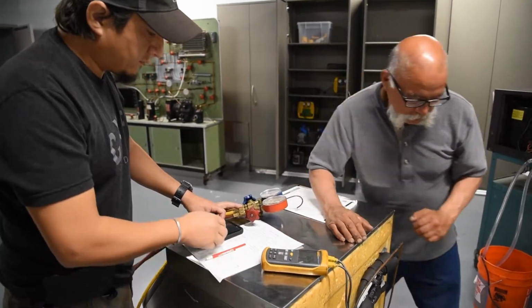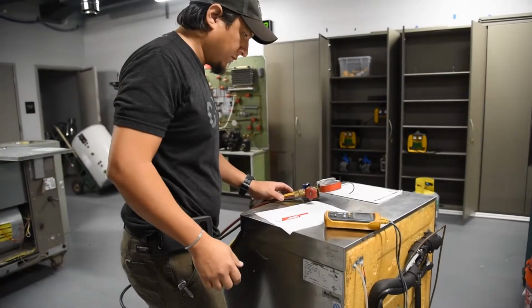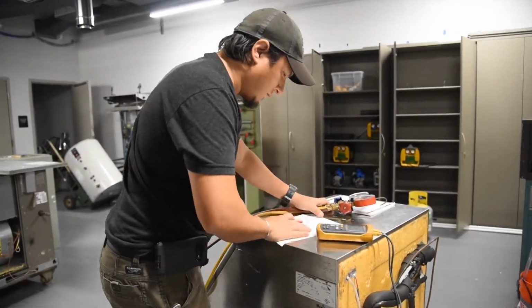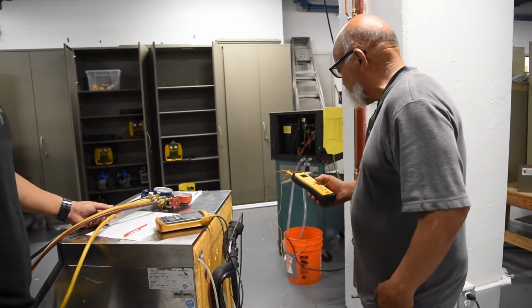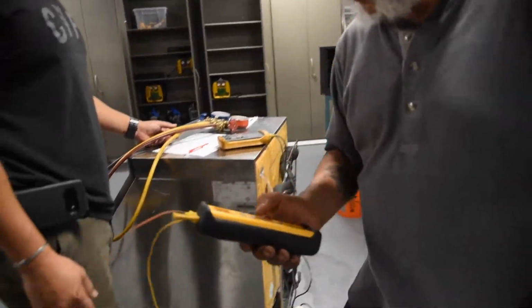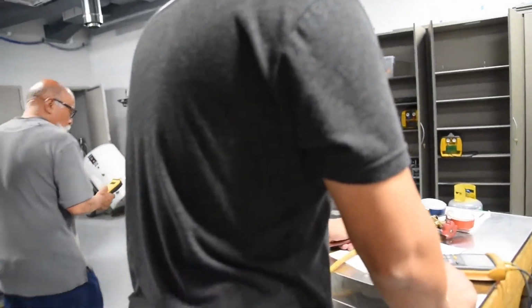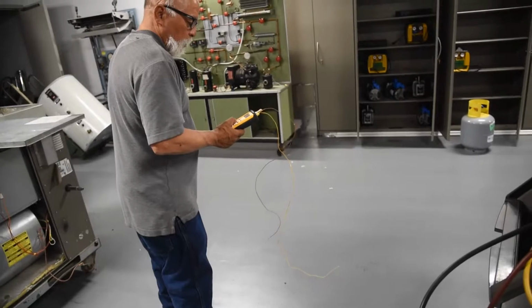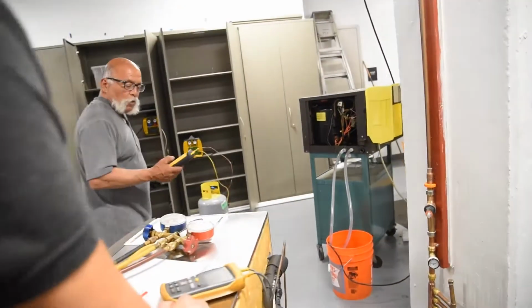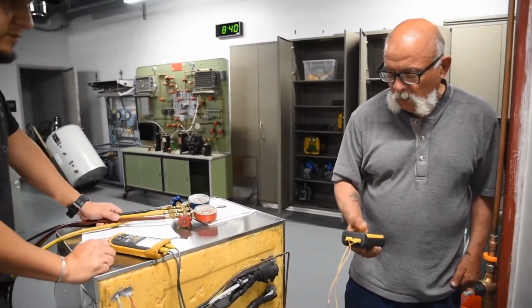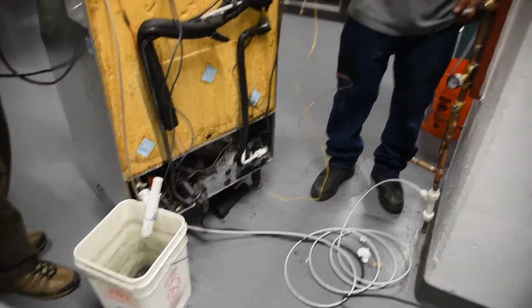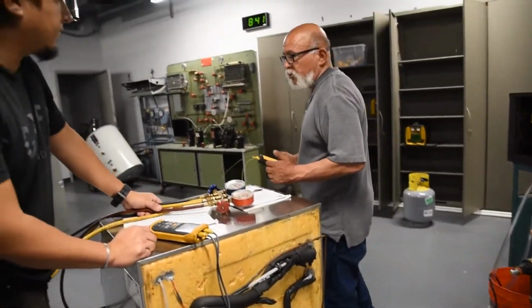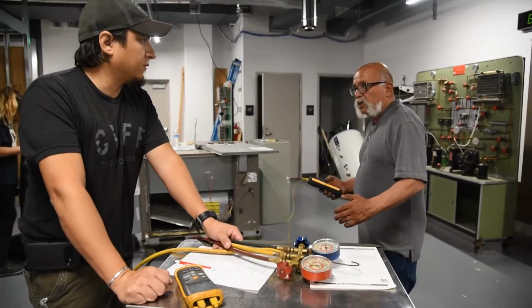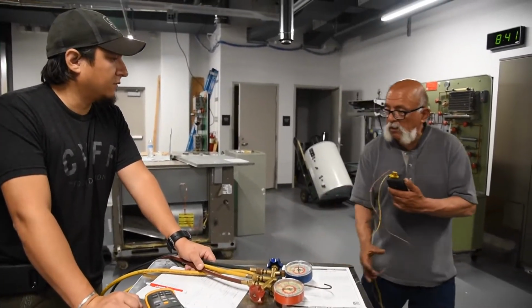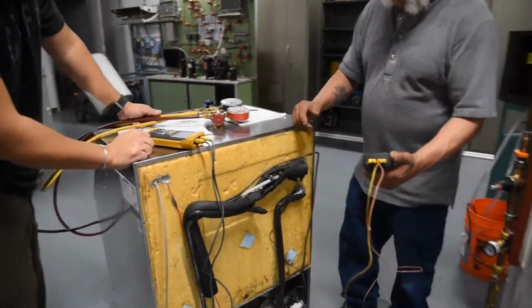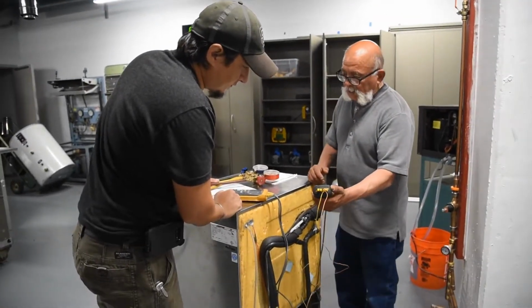The ambient temperature in the room is, let me get another meter. Ambient air flowing around the condenser is, we go over here, 73 degrees. That's our ambient temperature? Yes. Now what I was doing, I started taking the temperature here and I noticed it was a little bit warm, or warmer. Why would that be? That would be because of the condenser. So when you take temperatures entering the condenser, you've got to make sure that you're not real close to the condenser, or that you're not taking leaving air on the condenser. They check to see what leaving air really is.